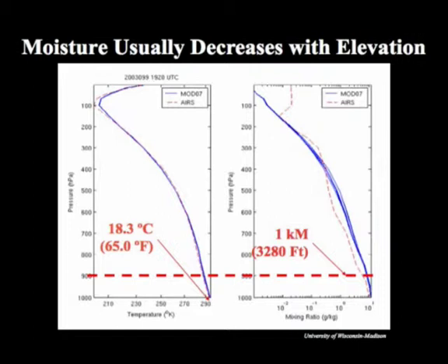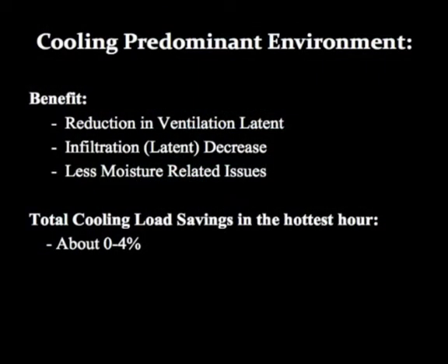Again, the moisture drops because the temperature drops, it tends to condense out of the atmosphere. In this case, the outside temperature is about the standard atmospheric temperature, so it's about 20 or so degrees Celsius. As the moisture warms up in the summer, you may not be able to drop as much moisture in the air because now the hotter air can accommodate more moisture. Why is it important? Because for those who live in hot and humid countries like Dubai, like Hong Kong, southern coastal China, etc., you will know that moisture is a big thing to deal with. Dropping moisture actually reduces the ventilation latent load, reduces the infiltration load, especially at the top part of the building, and also reduces the moisture-related issues. The total drop in the cooling load could be up to 0 to 4% depending on the amount of moisture.